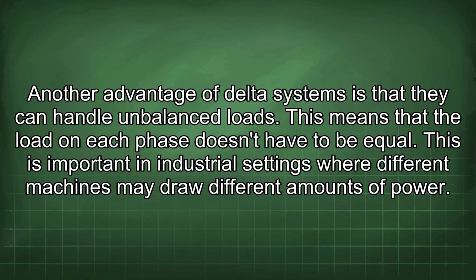Another advantage of delta systems is that they can handle unbalanced loads. This means that the load on each phase doesn't have to be equal. This is important in industrial settings where different machines may draw different amounts of power.